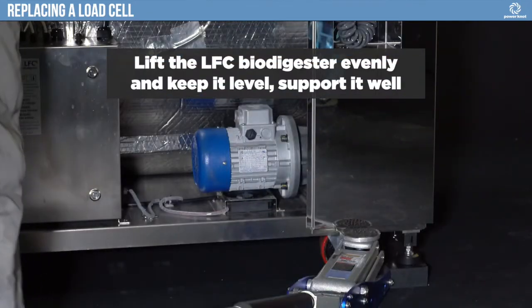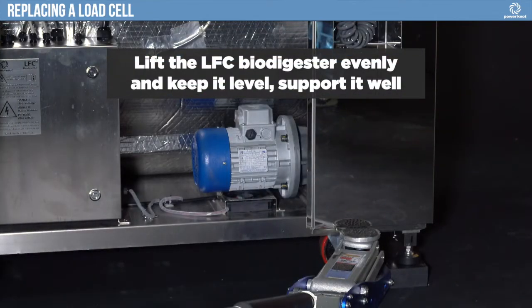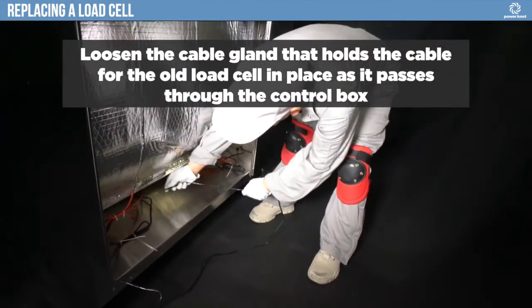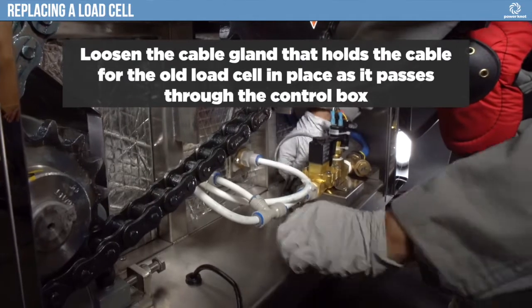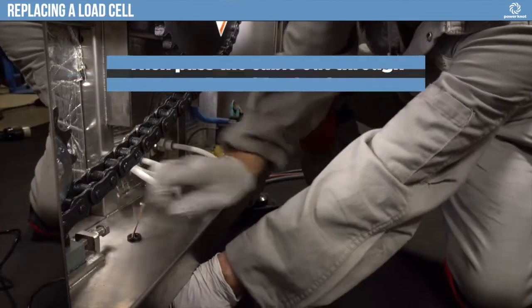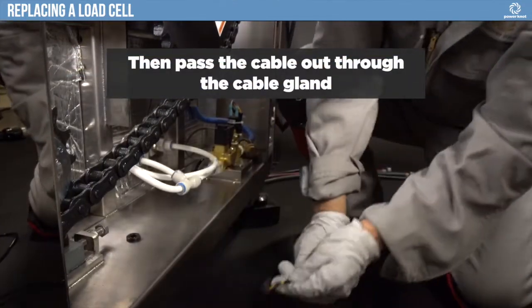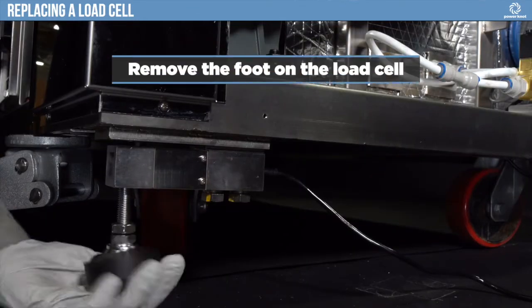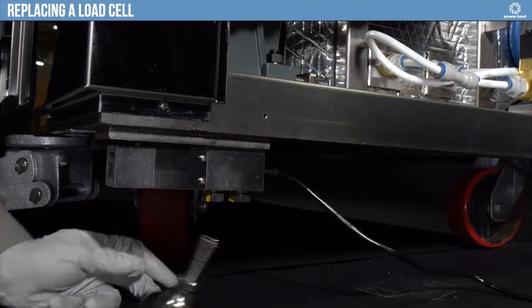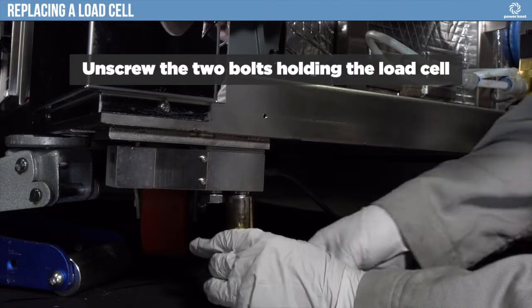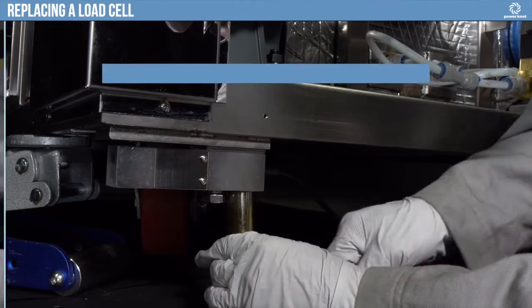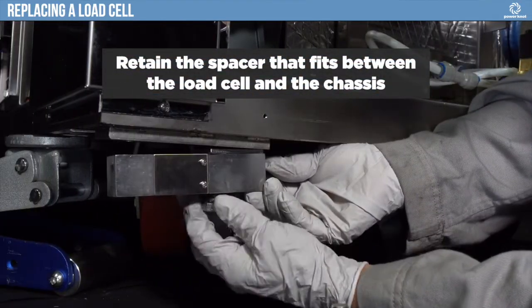Lift the LFC biodigester evenly and keep it level. Support it well. Loosen the cable gland that holds the cable for the old load cell in place as it passes through the control box, then pass the cable out through the cable gland. Remove the foot on the load cell. Unscrew the 2 bolts holding the load cell. Retain the spacer that fits between the load cell and the chassis.